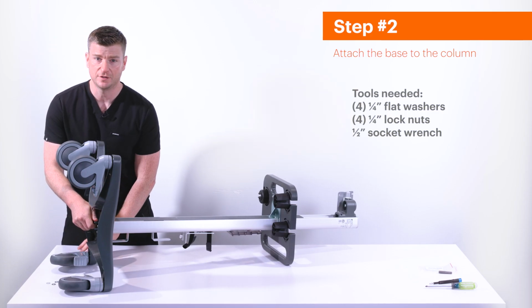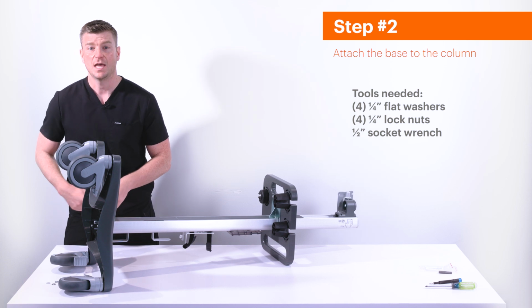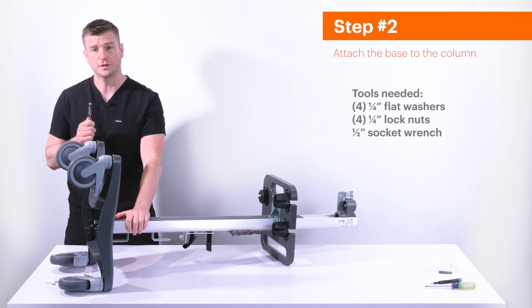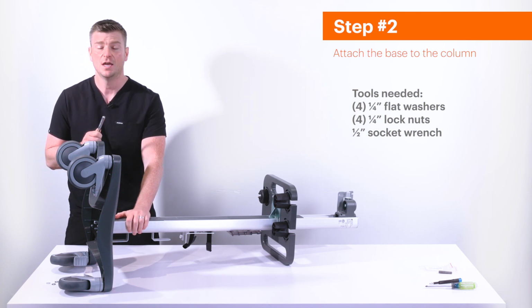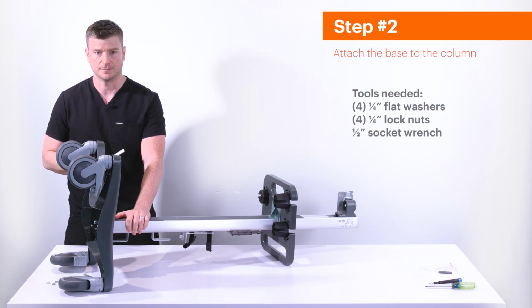Now grab your 1/2-inch socket wrench, and here's the key: you need to torque these to 75 inch-pounds to ensure a stable connection. Be careful not to over-tighten.